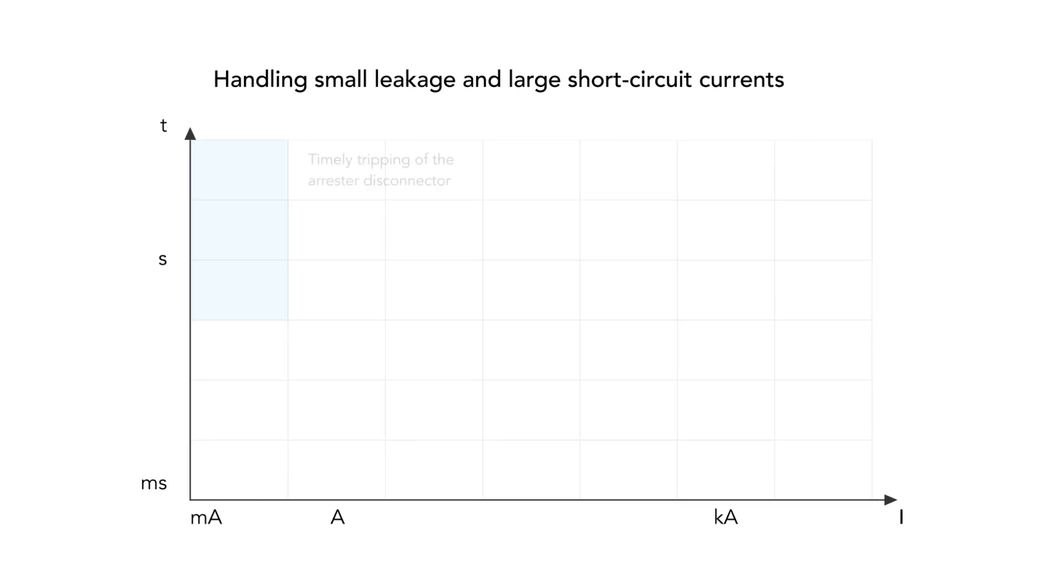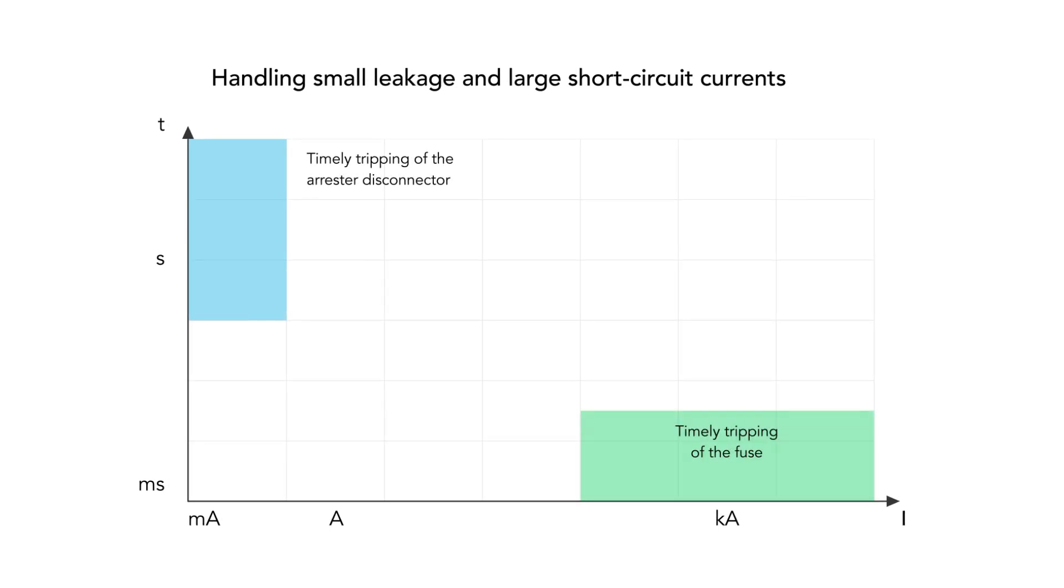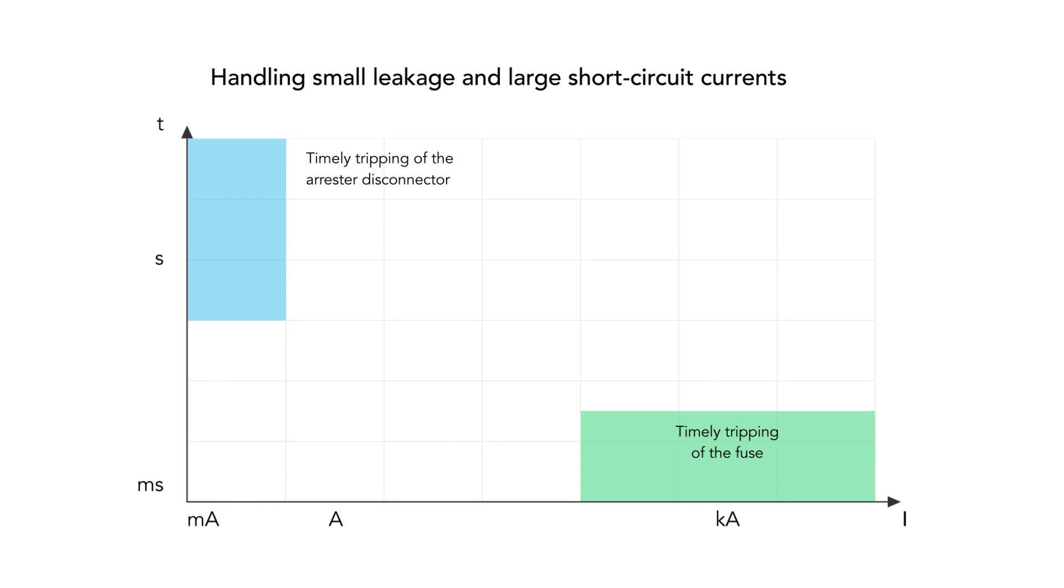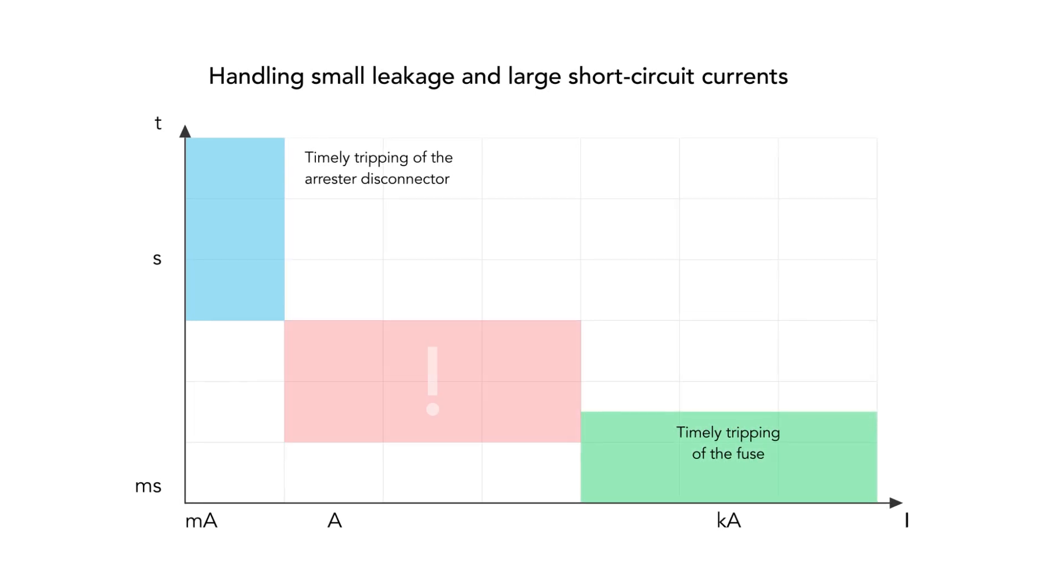The use of a fuse as a backup fuse for the arrestor or integrated in the arrestor has further disadvantages. Although the arrestor is disconnected from the mains in good time by the arrestor disconnector in the event of small leakage currents and by the arrestor backup fuse in the event of large short circuit currents, there is a protection gap.